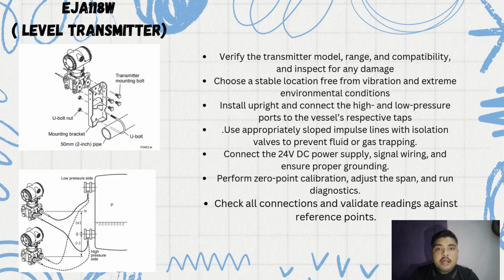Now I will explain the installation for the level transmitter. As you can see, we have two diagrams that show the details of how to install this transducer. First, verify the transmitter model, range and compatibility, and inspect for any damage. Second, choose a location stable from vibration and extreme environment conditions. Third, install upright and connect the high and low pressure ports to the vessel's respective taps. Fourth, use appropriately sloped impulse lines with isolation valves to prevent fluid or gas trapping. Fifth, connect the 24-volt DC power supply, signal wiring and grounding. Then perform a zero-point calibration, adjust the span and run the diagnostics. And the last one, check all connections and validate readings against reference points.